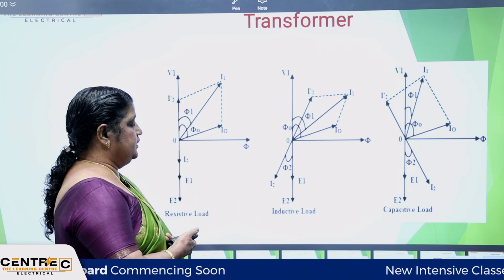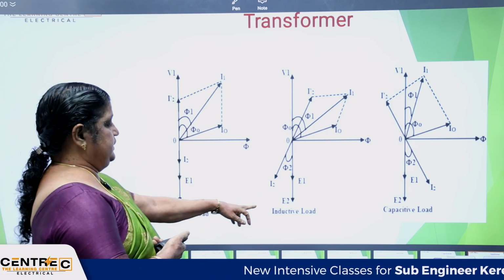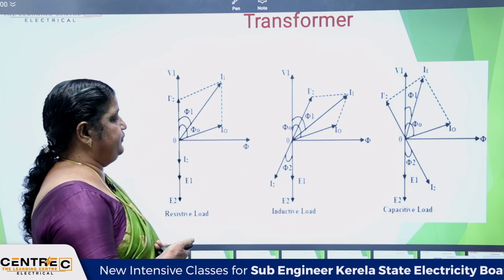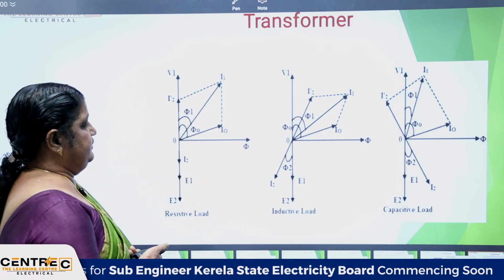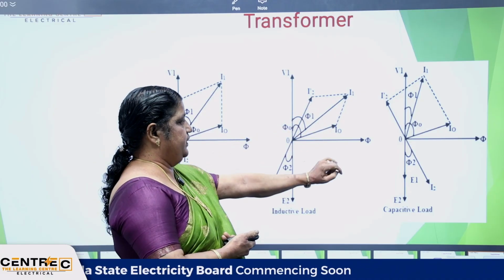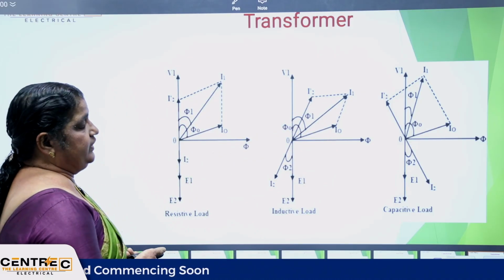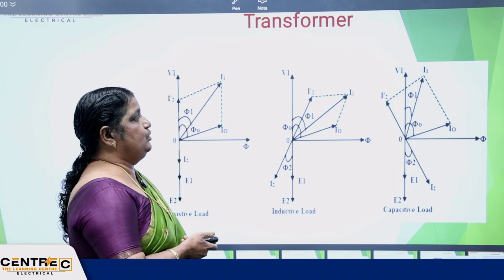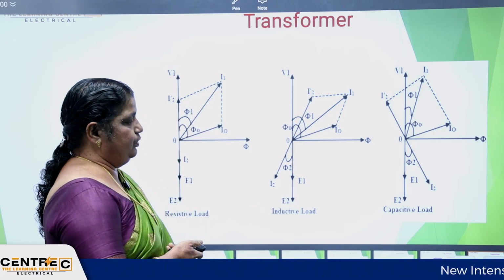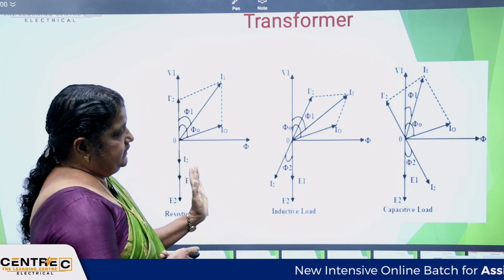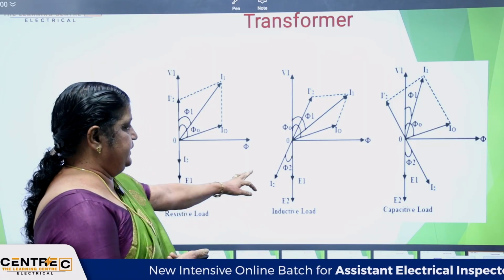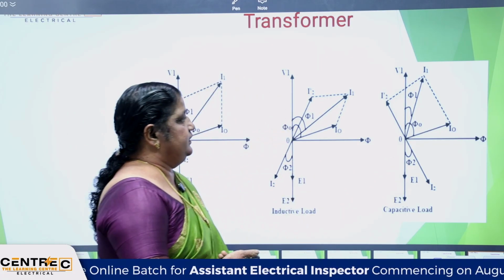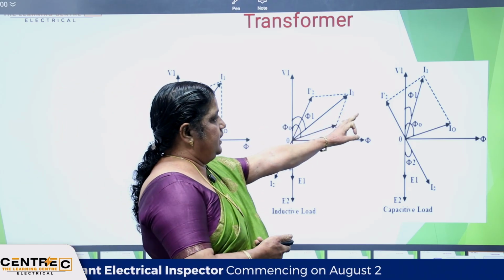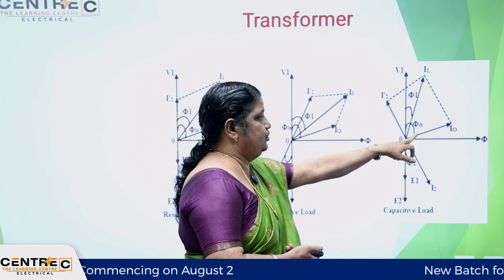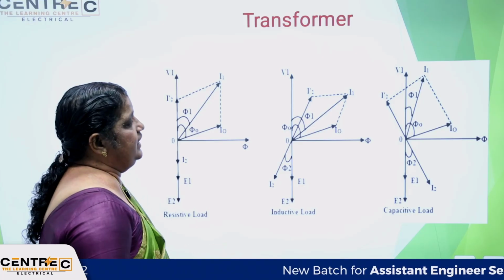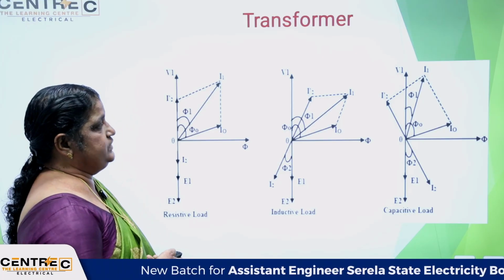But in the case of an inductive load, I2 and E2 have a phase difference, that is phi 2. I2 dash is this one, I0 is the magnetizing current, and the vector sum of I2 dash and I0 is I1. That is for the inductive load. But in the case of a capacitive load, a leading power factor is provided. Then phi 2 is I2 here, same as I2 dash. I2 is reflected into the primary as I2 dash, I0 is the magnetizing current, and the vector sum of I2 dash and I0 is I1.